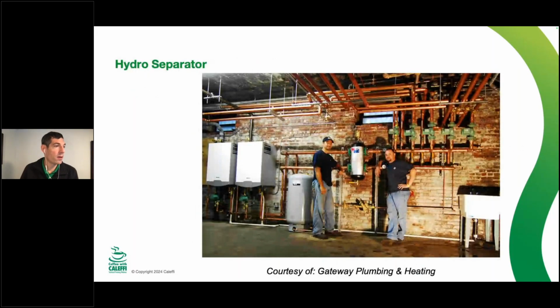So here's a good example. I can't quite tell what the pipe size is here, but we'll say it's 2-inch copper. If we did this with closely spaced tees, that could be wider than the shoulders of the two guys who are so proud of their work here. This is a great looking project. Absolutely could do it with a buffer tank or closely spaced tees. This is a pretty small envelope to be able to do this, and that's an advantage to the hydro separator. You can also pipe right into this with a 90, so we don't have that straight distance of pipe to the left or right like we did with the closely spaced tees.